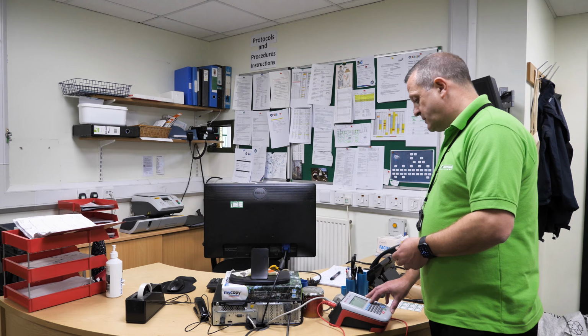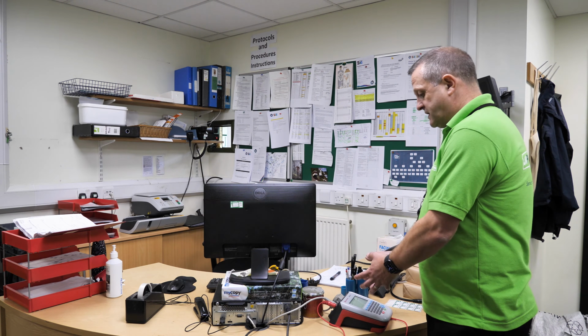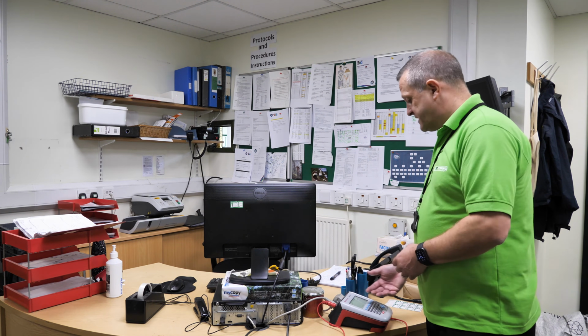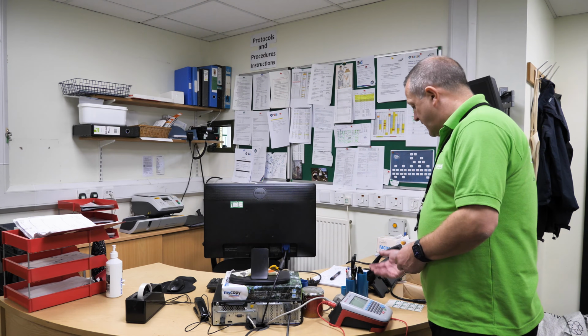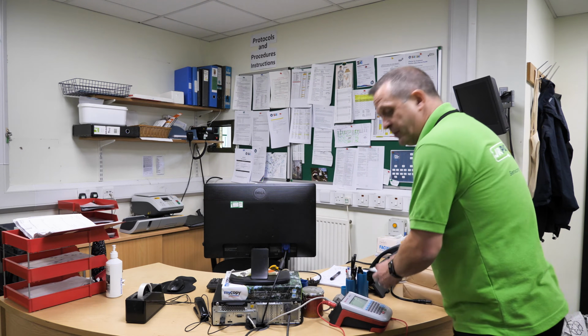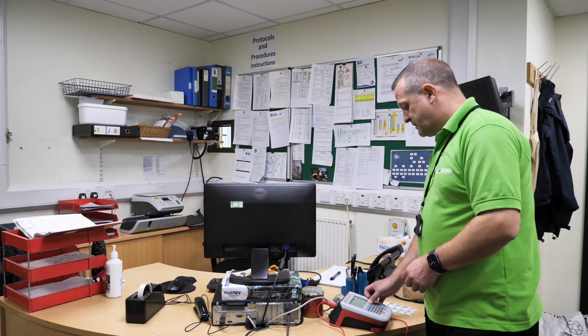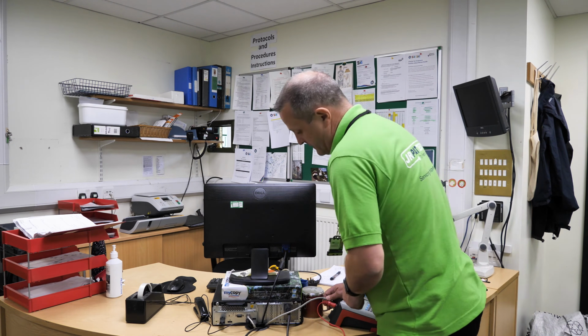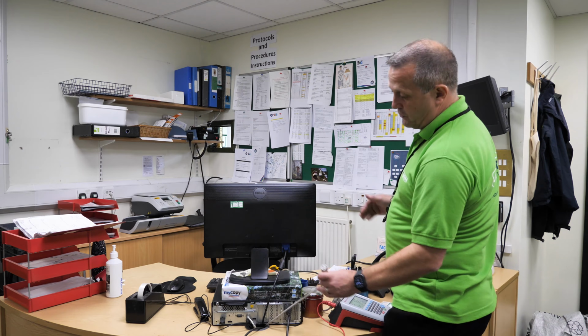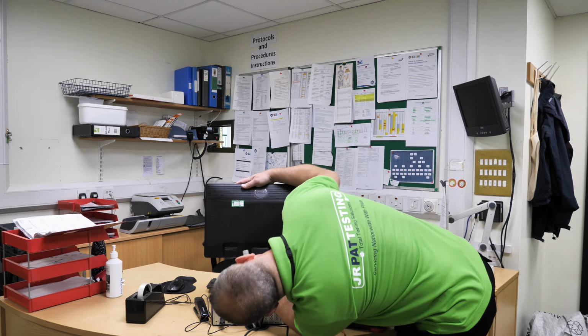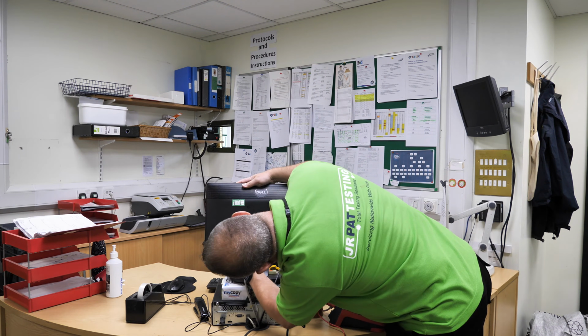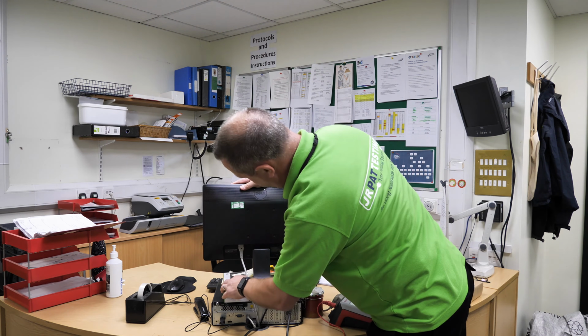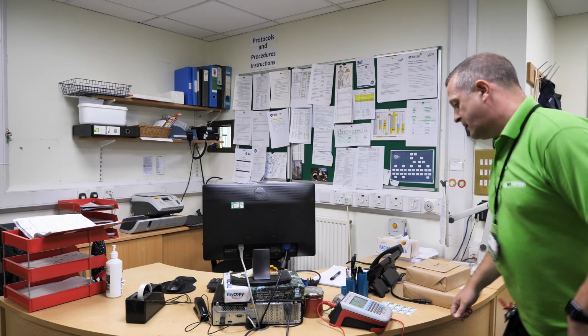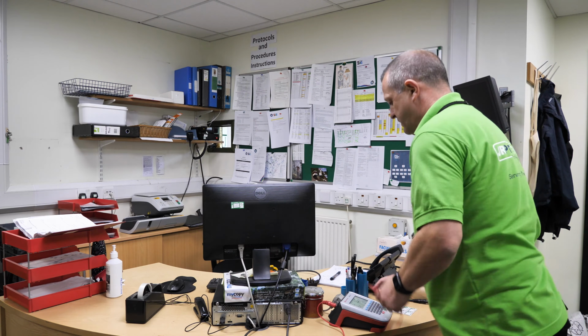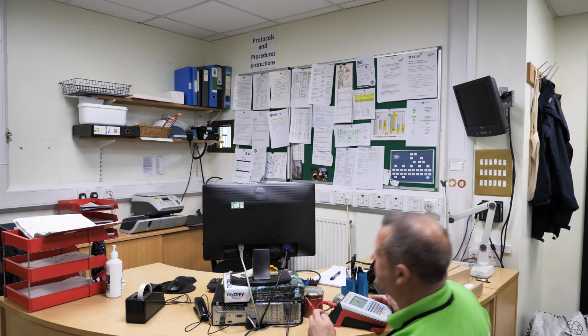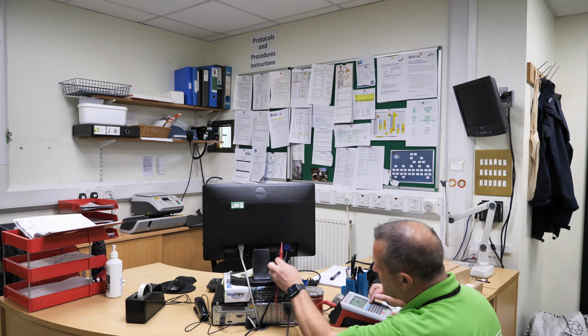So what we're then going to do, we're going to record that IEC lead's details onto the machine, and we're going to label it up accordingly as a pass. So that's all recorded, ready to go through. Going to leave the plug attached into the PAT tester machine, reattach the IEC lead to the monitor, and then we're going to conduct a Class 1 test on the monitor itself.